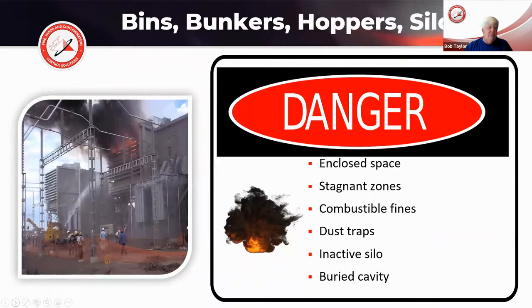Where we put that combustible material—biomass, coal, wood shavings, sawdust, or whatever—in the bins, hoppers, bunkers, and silos, some of the hazards we face are in closed spaces. Many of them have stagnant areas where material gets trapped. You get material sizing producing fines, and dust traps on structural steel and in areas that don't get attention in cleaning and removing. Then there's inactivity, which is increasing now, driven largely by current market conditions and the thought processes behind dispatching plants.